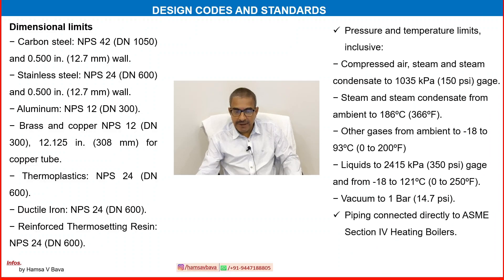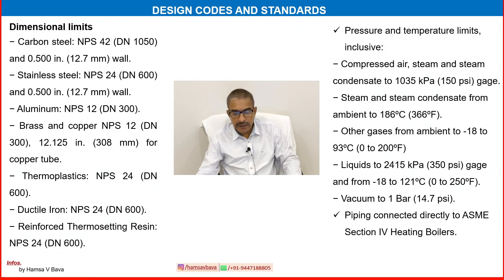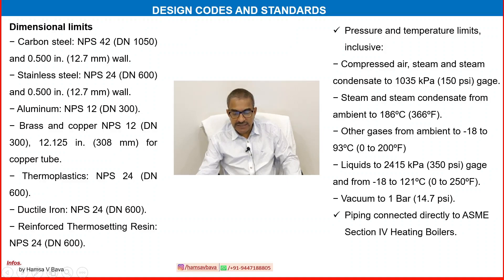Dimension limits and pressure and temperature limits are specified. For compressed air, steam, and steam condensate: around 150 PSI gauge, with steam and steam condensate temperature at 186°C. Other gases from ambient range of minus 18 to 93°C. Liquids from 350 PSI gauge and minus 18 to 121°C. Vacuum to 1 bar (around 14.7 PSI). Also included is piping connected directly to ASME Section 4 heating boilers.